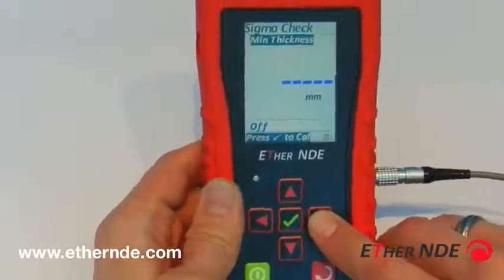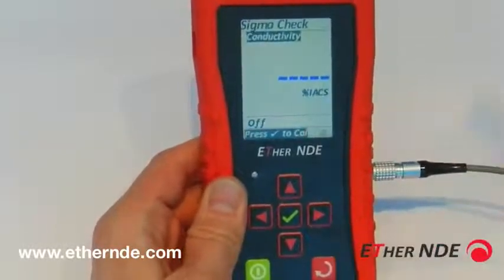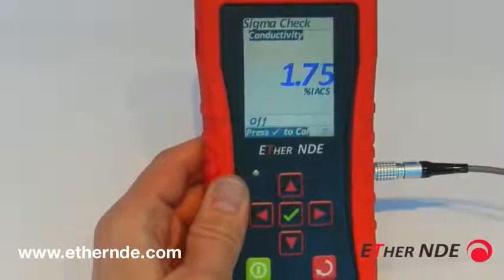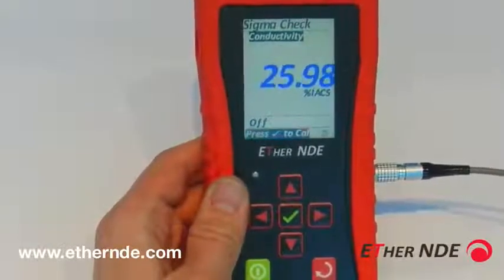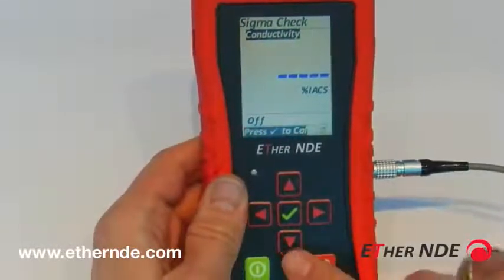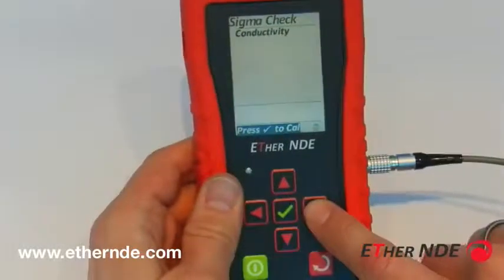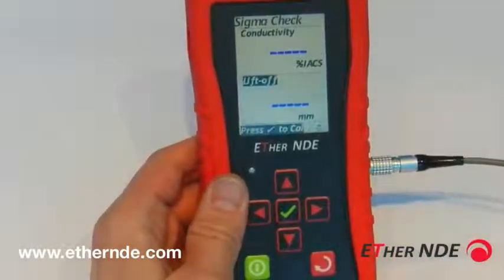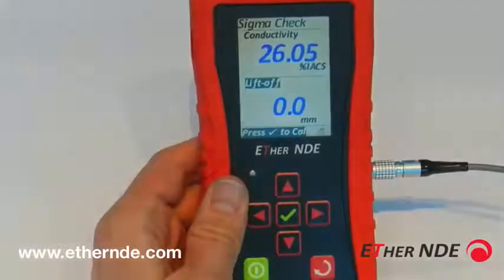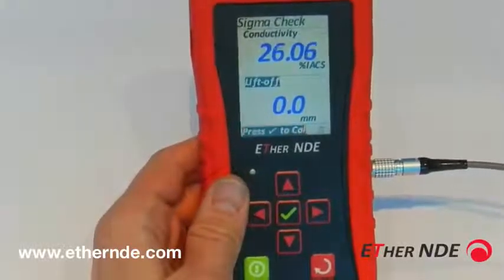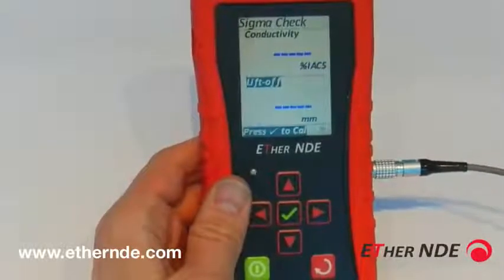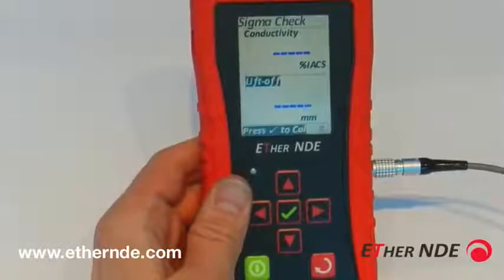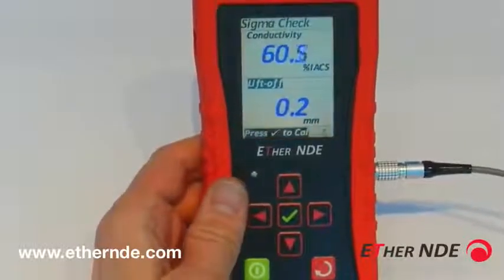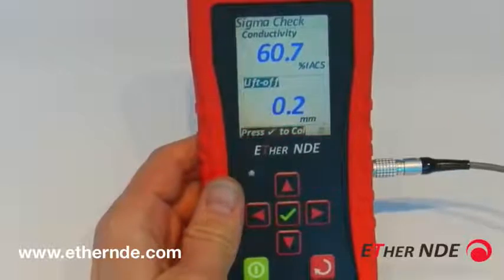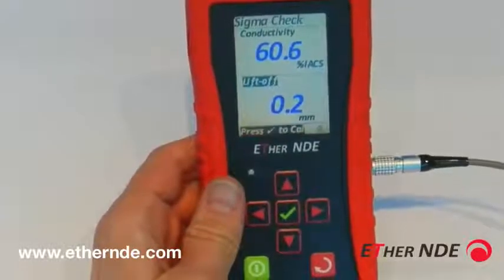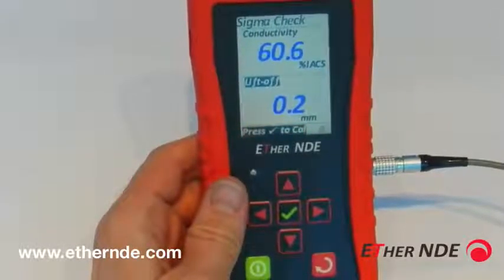In fact, if I go to conductivity and display a value, see the numbers are quite large. If I then turn the bottom screen on, the numbers are now slightly smaller. Now, if I purposely generate a liftoff, as you can see, you can have the conductivity displayed in one half of the screen and the liftoff or coating thickness on the bottom half.